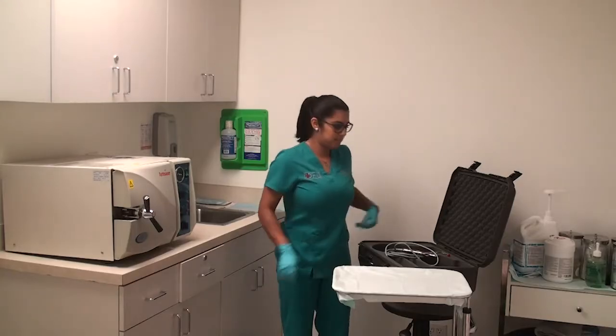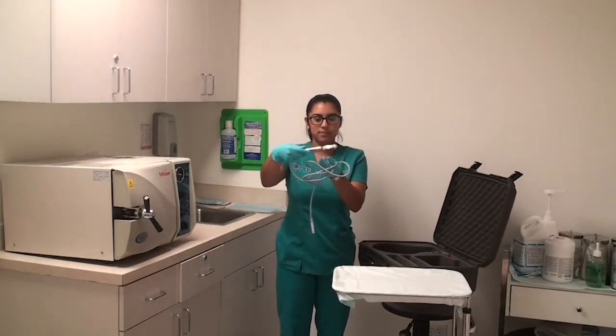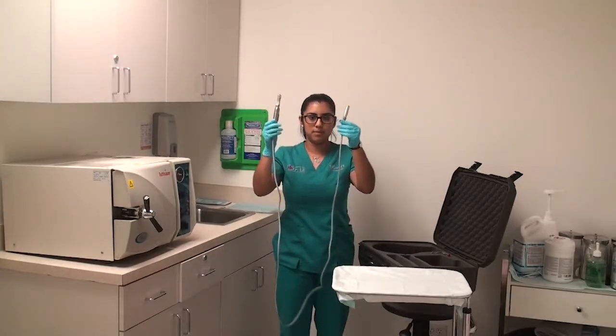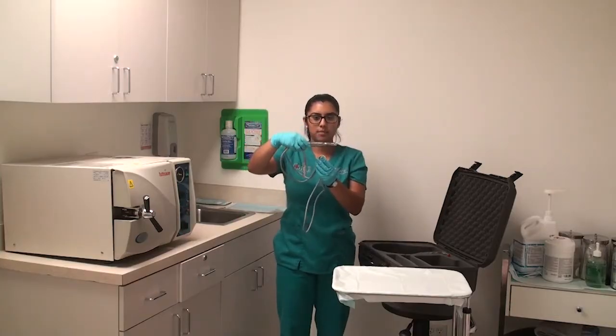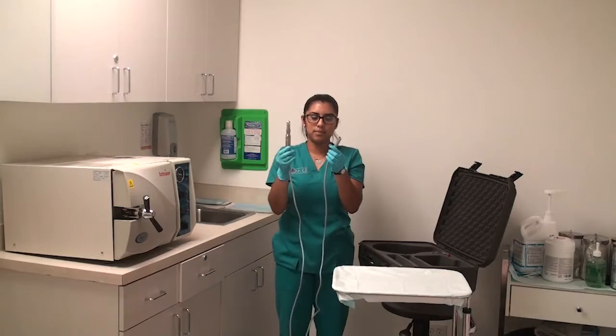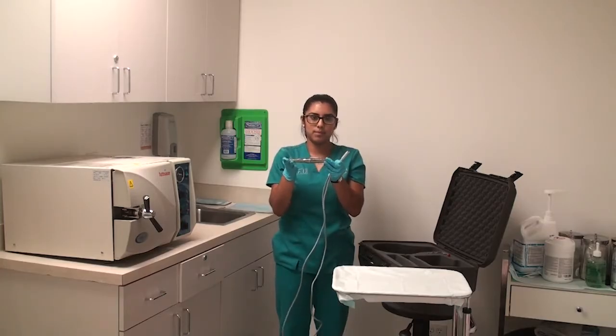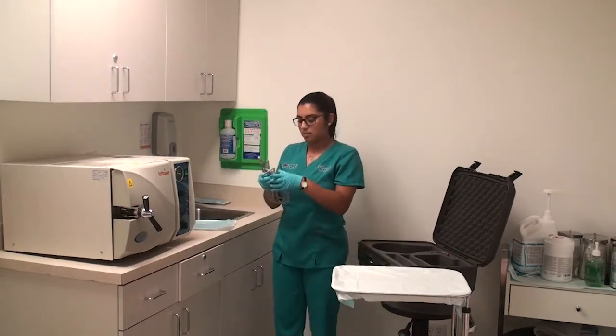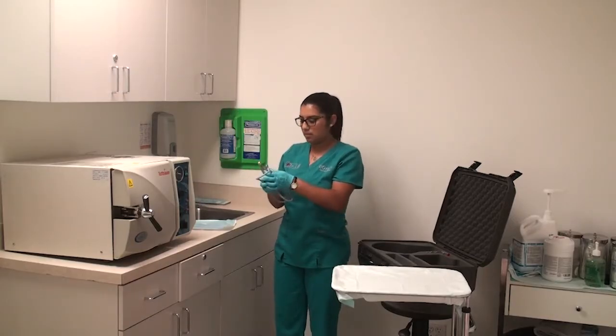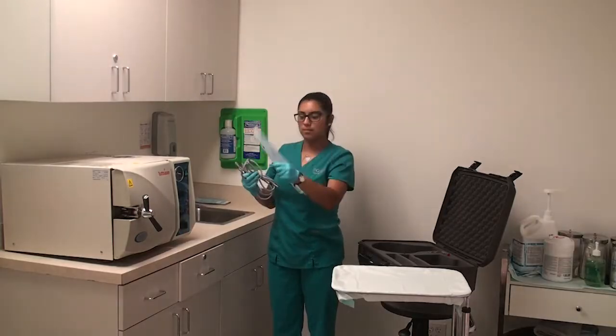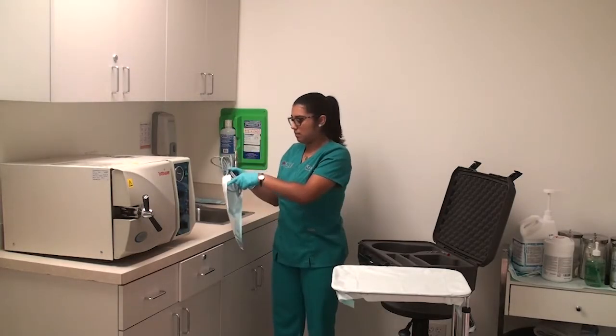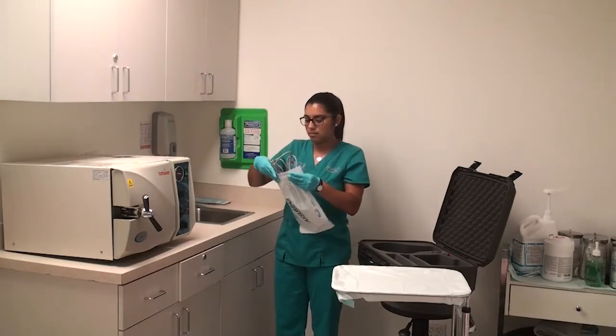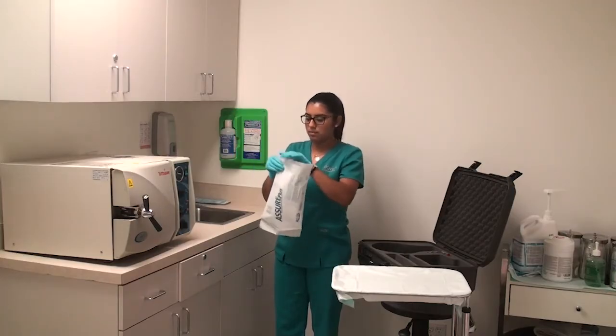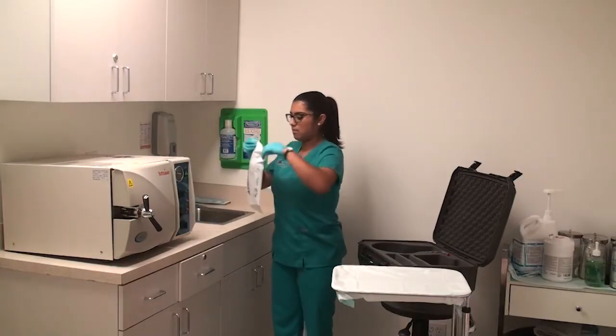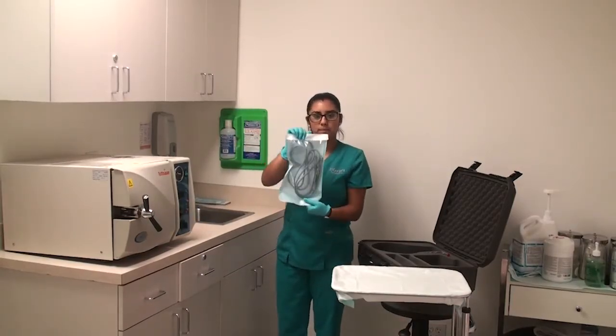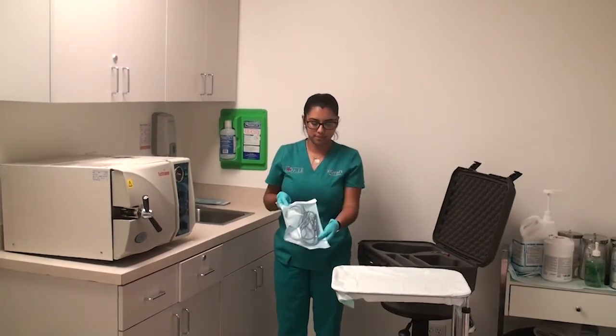When you receive your Dr.UGraft hair transplant system, prior to using it, you need to sterilize 2 key components. The first one is the Dr.UGraft Nurture handpiece, which comes with a cord attached to it. The cord and handpiece are to be sterilized together as a single unit. They are not to be detached from each other. They are always to be maintained and used as a single unit in all circumstances. You would coil up the cord, make it portable, and then put it in a sterilization bag. You want it to be sealed as seen in this example. The whole unit, handpiece and cord, is placed in the autoclave machine.